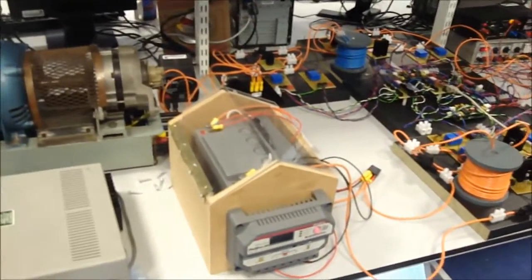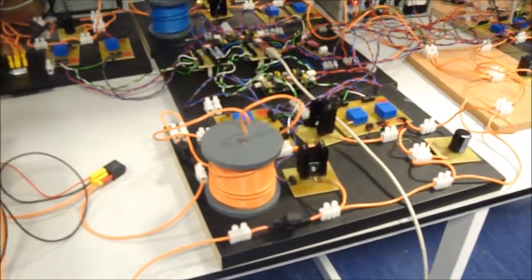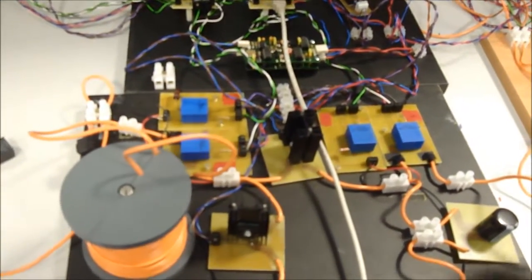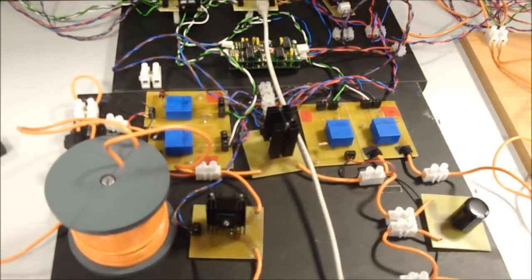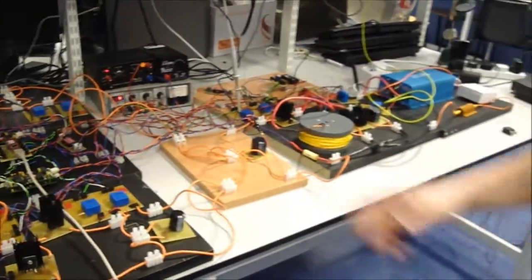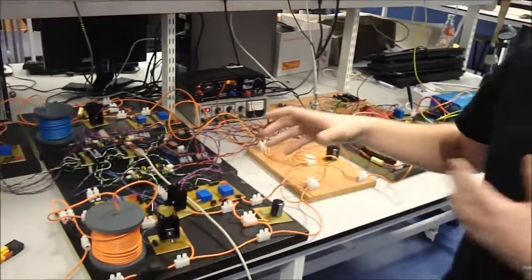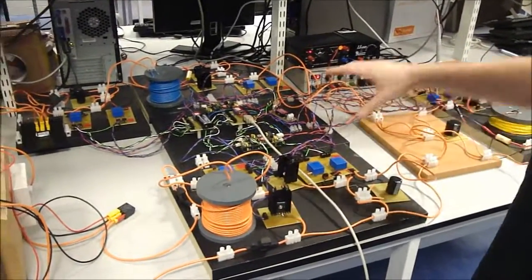If we come back along the system, we now have this battery storage here. This battery storage is controlled by this bidirectional converter here. The bidirectional converter is basically the main management system, the way of managing the power. What happens is when the wind generation is greater than the load requirement, the bidirectional converter goes into battery charge mode. It then takes power from the bus and charges the battery.